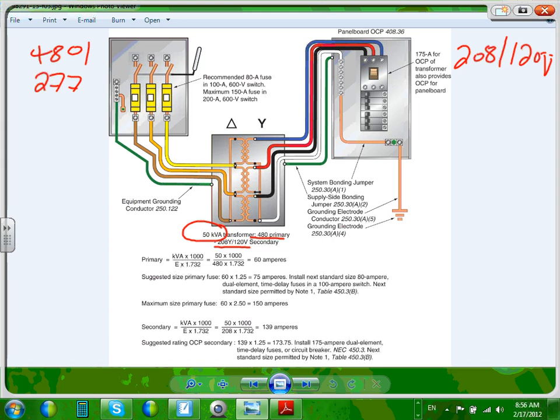So the primary is actually a delta. Well, it's not a delta, but it's 480 volt. We don't need a neutral on the primary. Any question, guys, about the primary 480? Fuse disconnect coming to the transformer, going to the 208/120 to feed the receptacles. Feed receptacles. Okay, who cares? Again, we will be doing a lot of calculation like this.